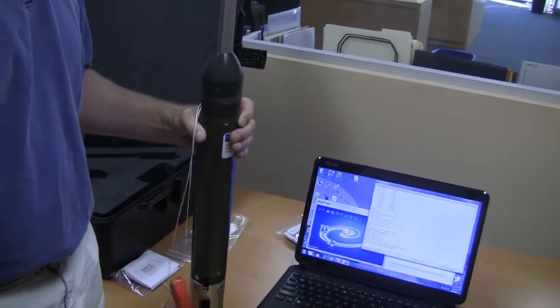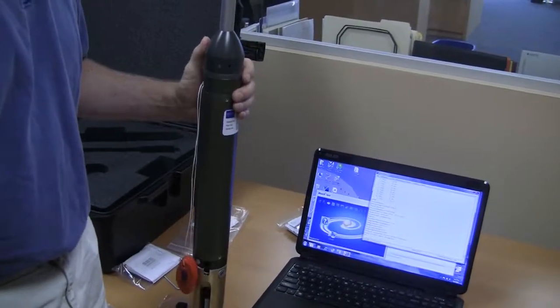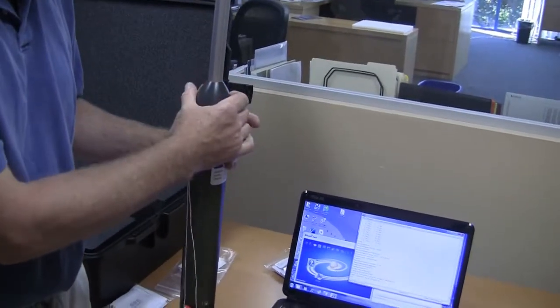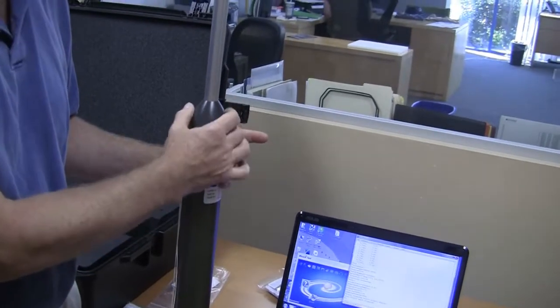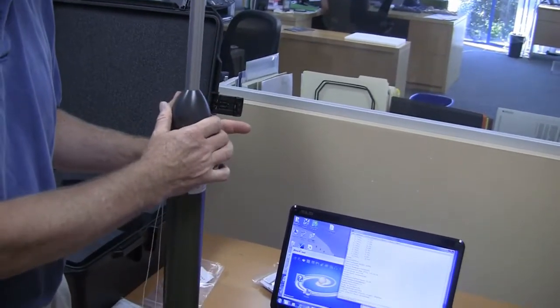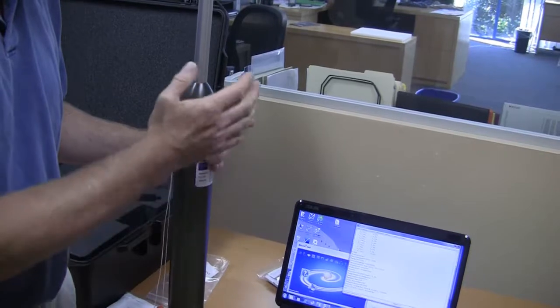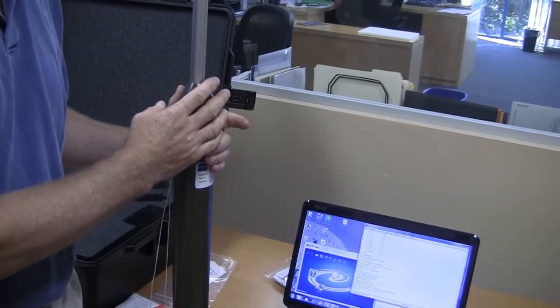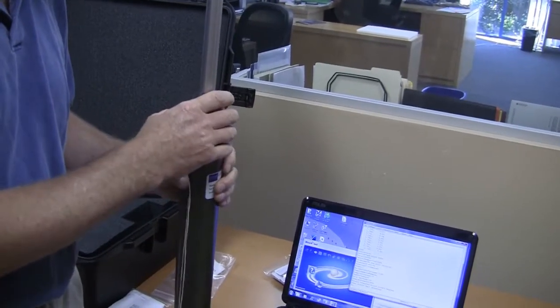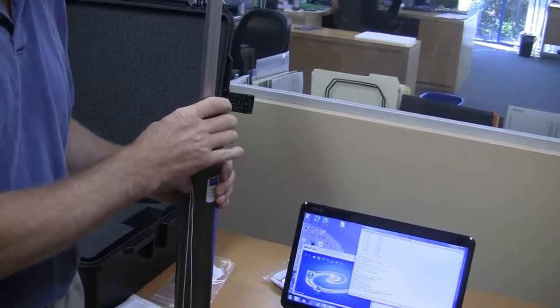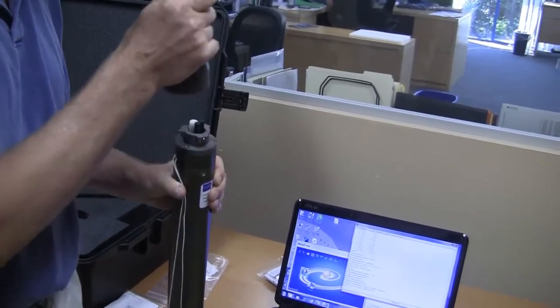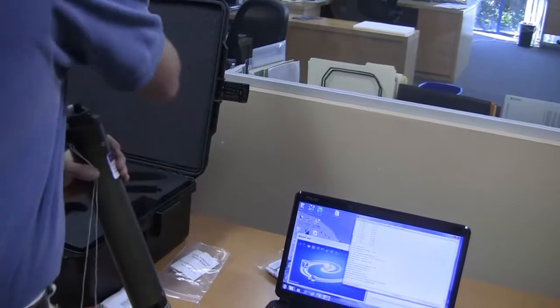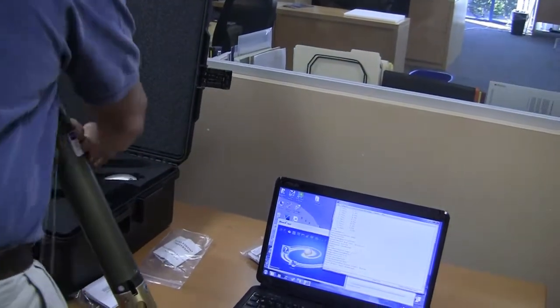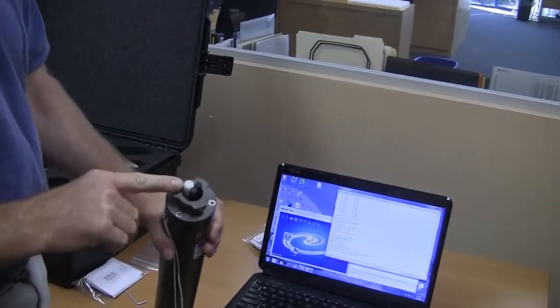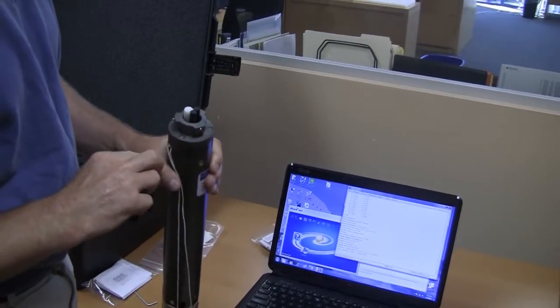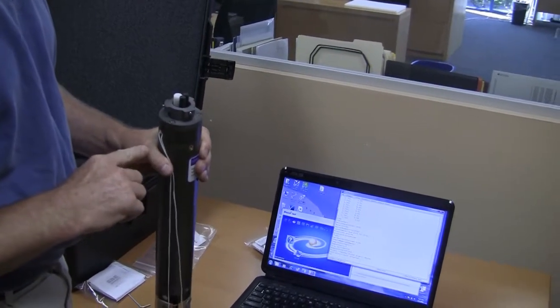Also, the one thing you won't be able to do is actually talk to the probe in this state, because the aluminum bulkhead of the tail spool covers up the Bluetooth antenna, so you will not be able to talk to the probe with the tail spool connected. In order to establish communications and download data, you have to remove the tail spool, and now that exposes the Bluetooth antenna, which allows you to talk to the probe wirelessly.